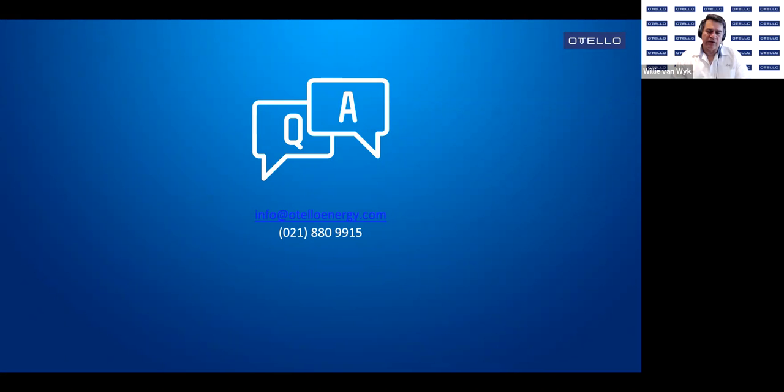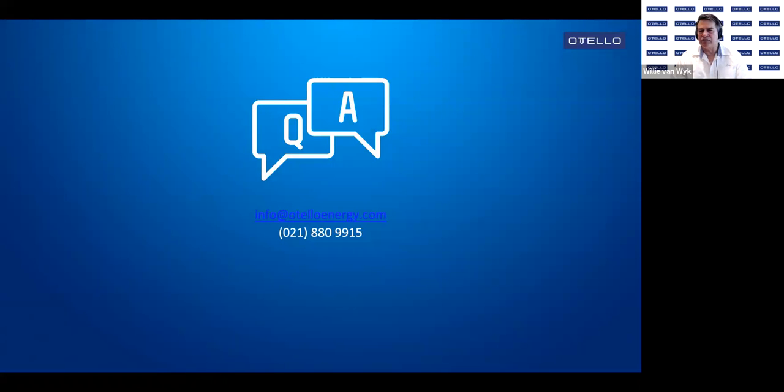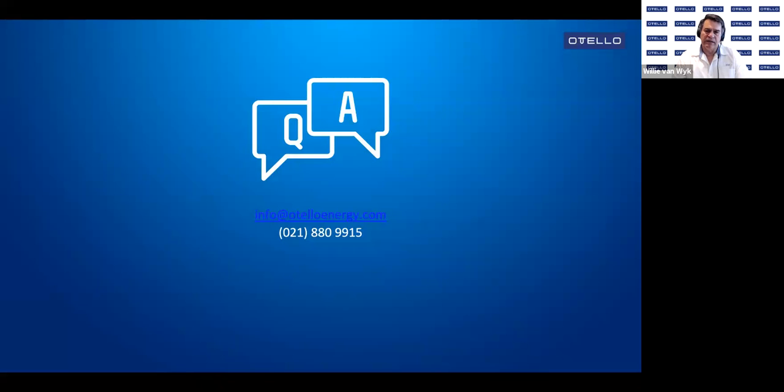Phil, protection is personally not my strong point, so my apologies on the real application of the protection side. What I can say is that on the device itself, the fact that we are time synchronized to within plus minus 100 nanoseconds from absolute time, the micro synchrophasor that has been recorded has very small phase angle resolution. I think it's a 0.1 degree resolution. The question is how do you integrate with the differential relay, especially the communication, so that you keep in mind we've got an operating system and the operating system has some delays. On the accuracy of the data itself, all is there. If you want to do it on the device itself, we can instantaneously respond to it. The device has got four relay outputs so you can directly control four outputs and at the same time also four digital inputs, so you can control and verify what's happening.